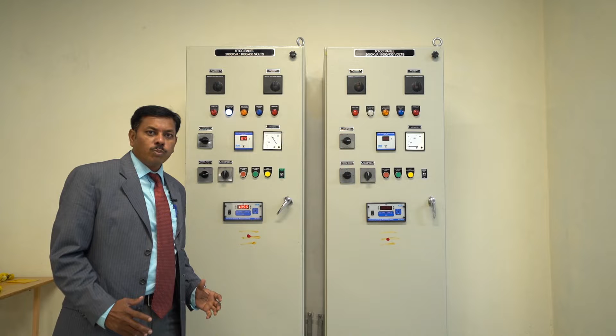We are in the ground floor main electrical room where the electrical LT supply system is being distributed to the whole of the building, and one part of it is being fed to our utility panel where the utility services are being handled like lift services, PHE pump panels, chiller panels, and also STP and WTP pumps, where these services are being catered through this utility panel.